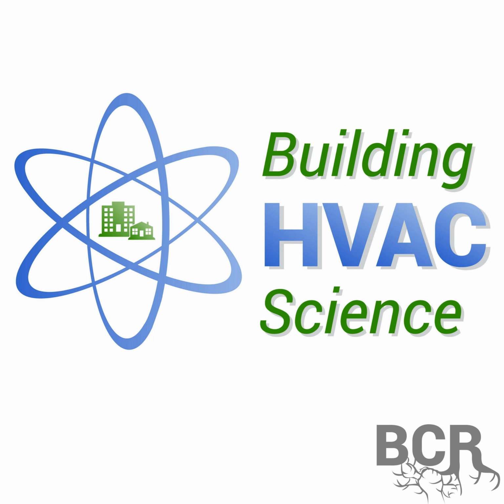And knowing the rate at which this energy transfer is happening can tell us an awful lot about how our HVACR systems are performing. The amount of energy transferred is proportional to the mass of the air that's flowing, or its mass flow rate in engineering terms. This thankfully leads us now to a more familiar term, CFM, or cubic feet per minute of airflow, which is really an assessment of the mass flow rate of the air. Okay, so all we're looking for in airflow is to measure the CFM. We're good, right? Well, not so fast.